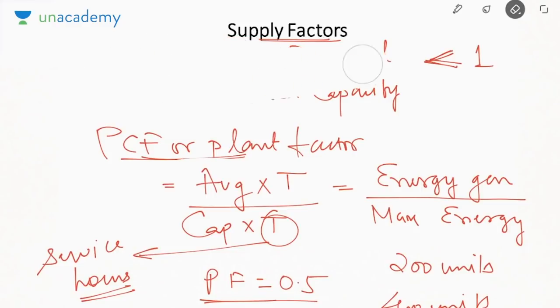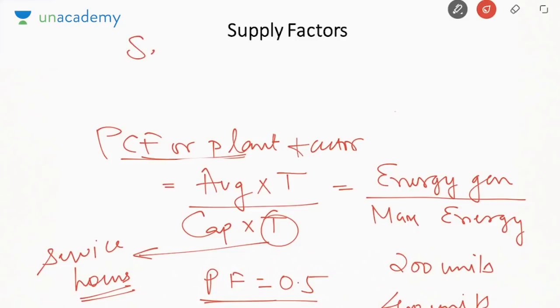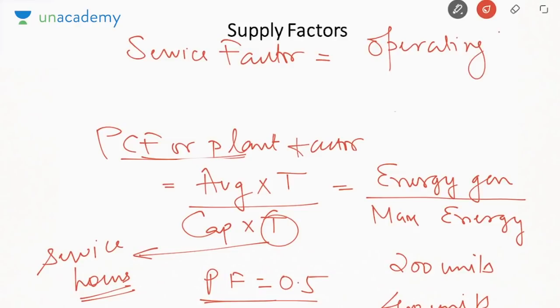Next is your service factor. Service factor is similar to duty cycle. It is equal to operating hours upon total hours. Suppose in 24 hours I work only for 8 hours, then my service factor will be 1/3. So it indicates a duty cycle, that is on time divided by the total time. That is my service factor.